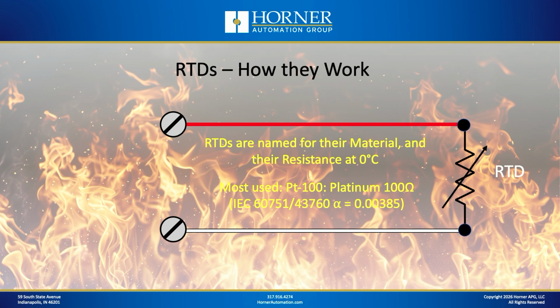Now, RTDs are named for the type of material they're constructed from and for whatever the resistance value is at 0 degrees C. The most common one by far is platinum 100 or PT100. So it's constructed of platinum and it has a resistance value of 100 ohms at 0 degrees C. And there's an IEC standard that's been in use for many years. When my career started, there was a much larger variation in terms of the number of RTDs that were available on the market. Most people have standardized for most industrial applications on PT100s with the specification you see there on the screen.